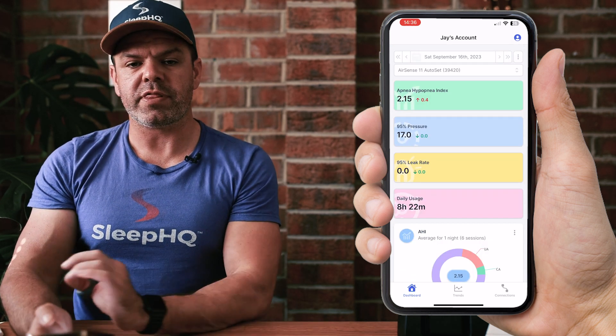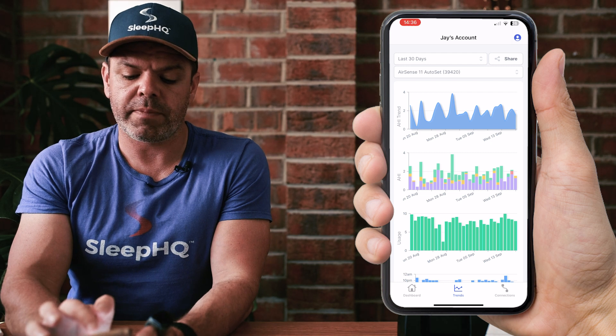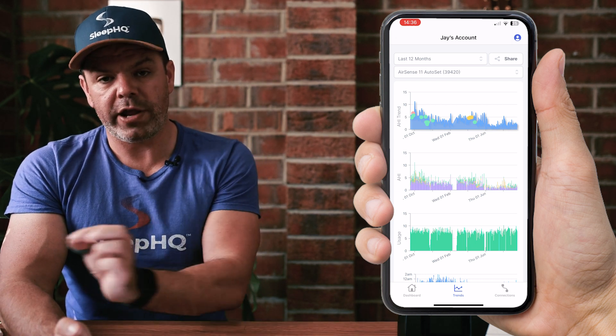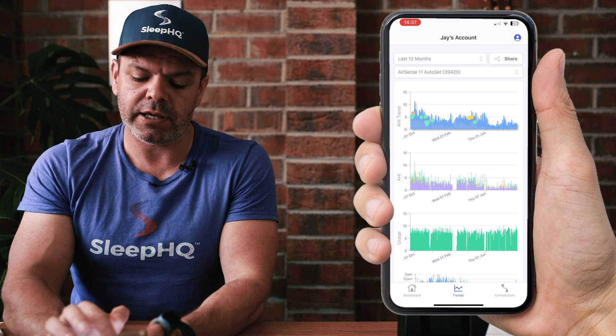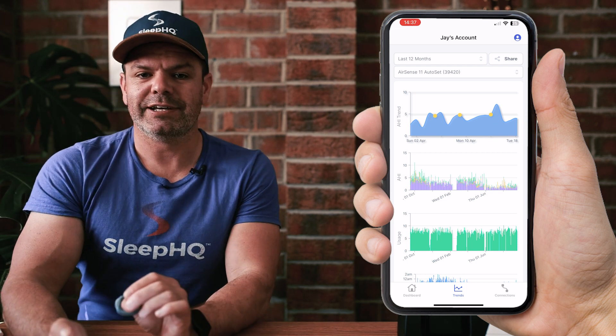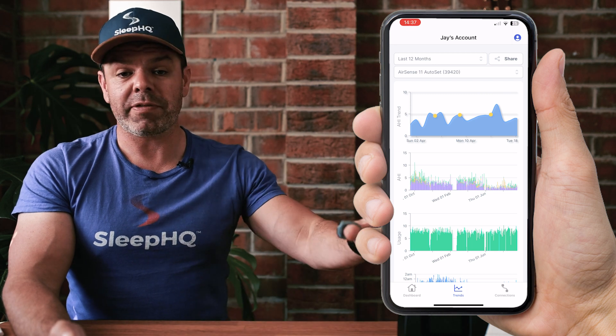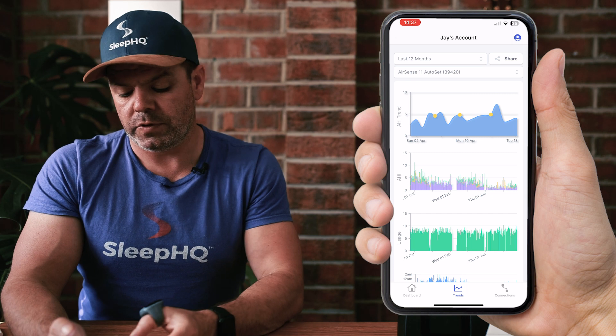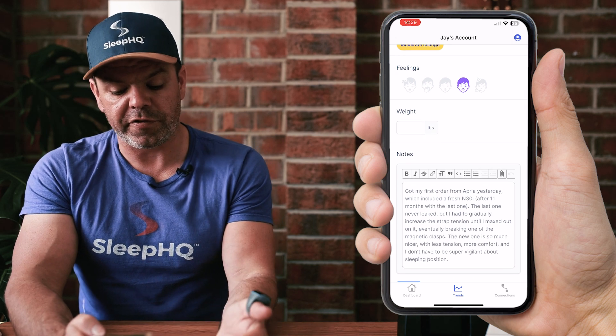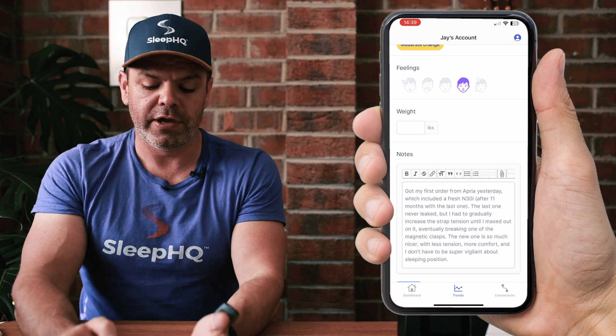We can also view our sleep and therapy trends by clicking the trends tab at the bottom. There's not much of a trend visible at 30 days, but let's change the time frame to 12 months — and there we go, I can clearly see a downward trend in the AHI, great stuff. You can see three yellow dots — these are journal flags. Flags are anything you want them to be: maybe you changed your mask, changed pressure, changed CPAP therapy mode, were sick, or lost some weight. You can create a journal entry — here's one that says 'got my first order from APRIA yesterday which included a fresh N30i.' He's put in a note and now he can track the changes on the trend view.